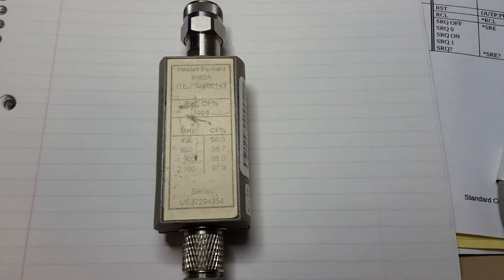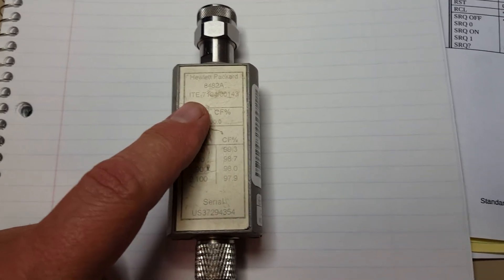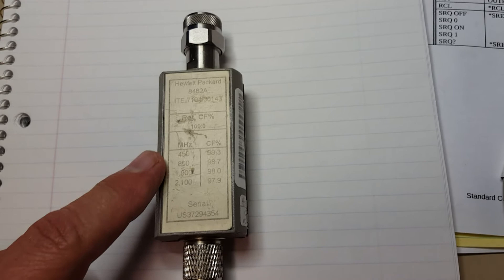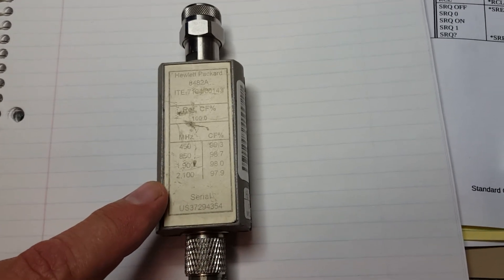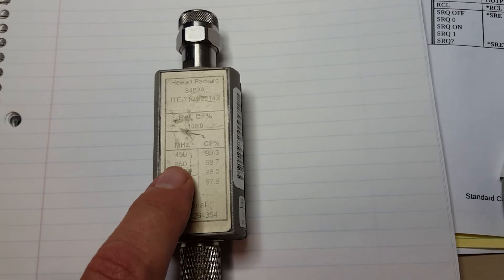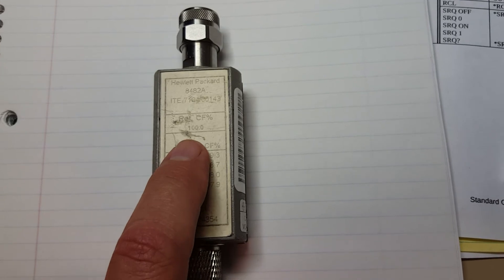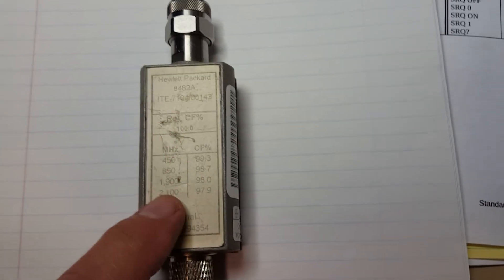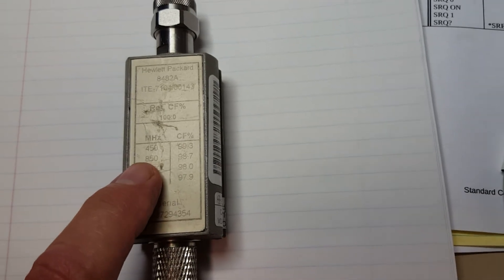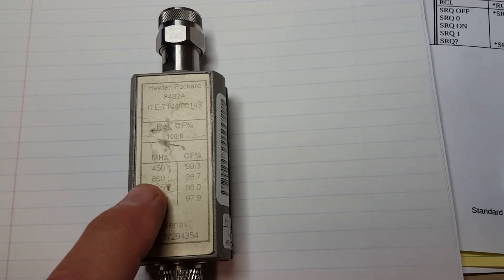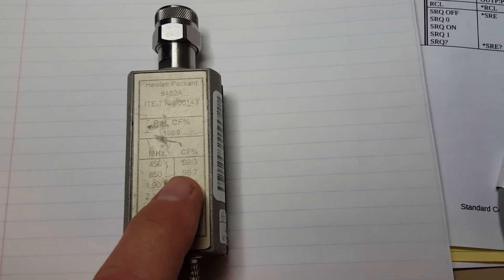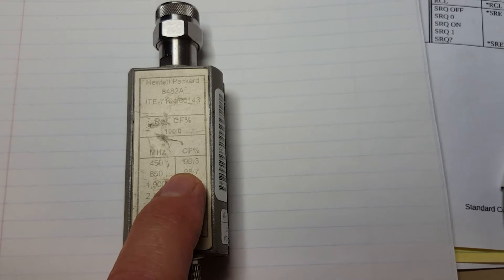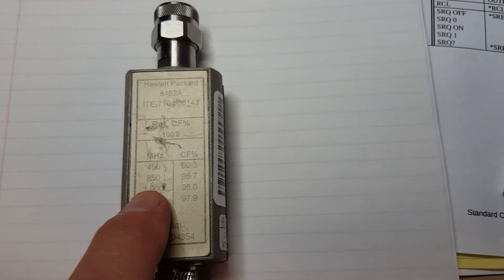A word about the sensor here: this is the HP 8482A power sensor. On these sensors, they have what are called calibration tables. If I was using this sensor below 450 megahertz, my calibration factor is 100. If I go higher than that, I have to use a different calibration factor. At 450 or higher, I would set the meter for a calibration factor of 99.3.